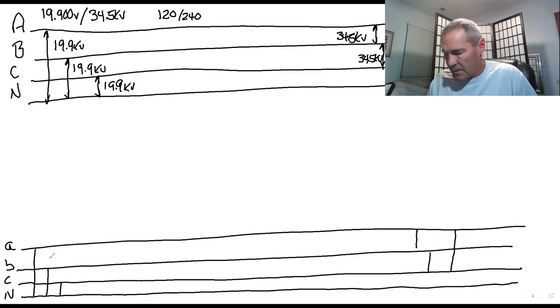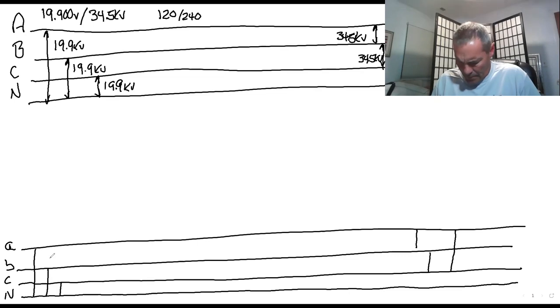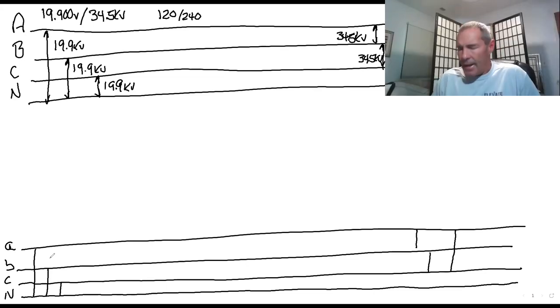All right, so I don't want to mess you guys up. There's a certain way that I draw closed delta. If you want to study the sheet and do it by the sheet that's in D2L, you can do it that way. I do it a little bit differently here, and you're going to see it in just a moment. It doesn't hurt either way. You remember on closed delta, open delta, which leg was the high leg, A, B, or C? The power leg, on open delta? C. C was. And I kind of like to keep it that way.